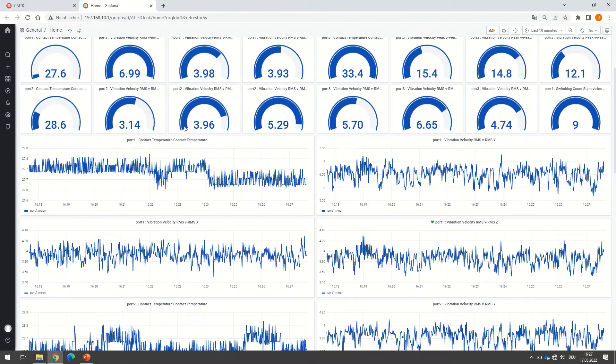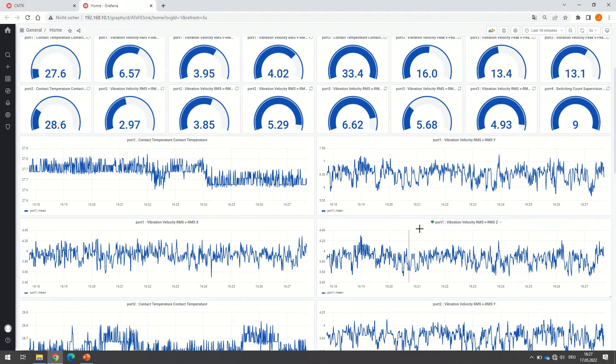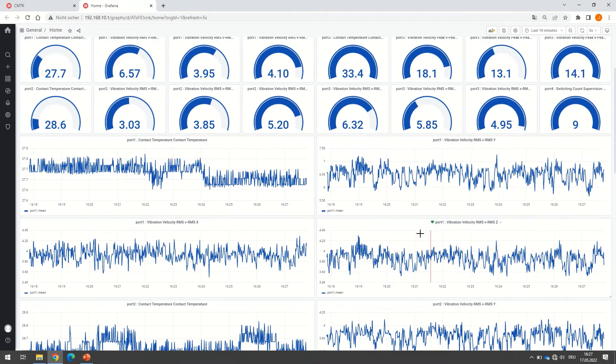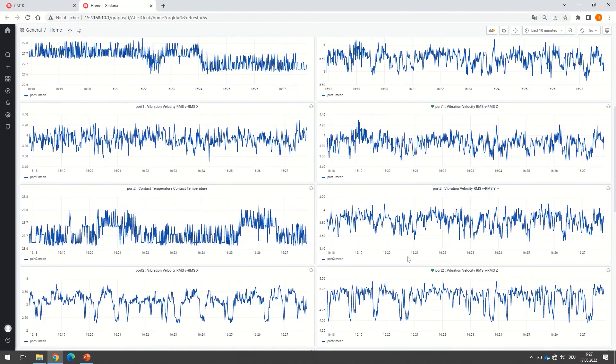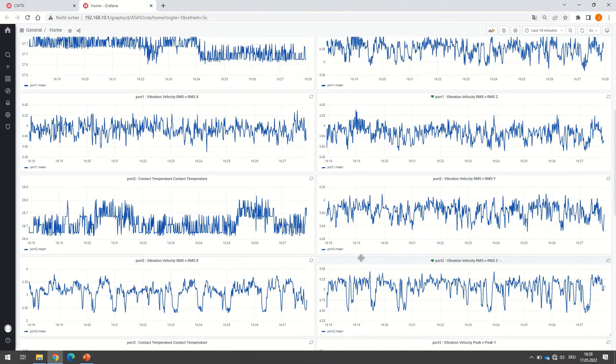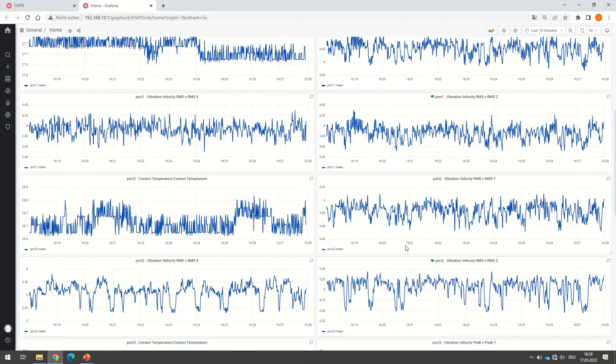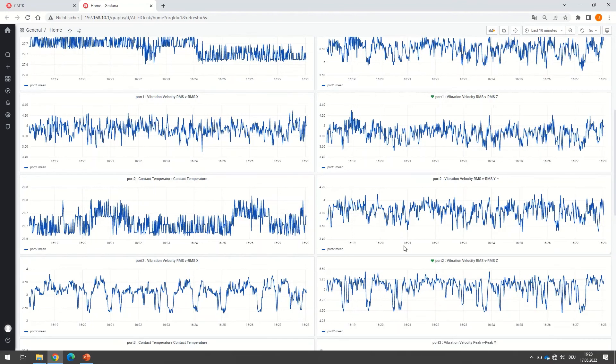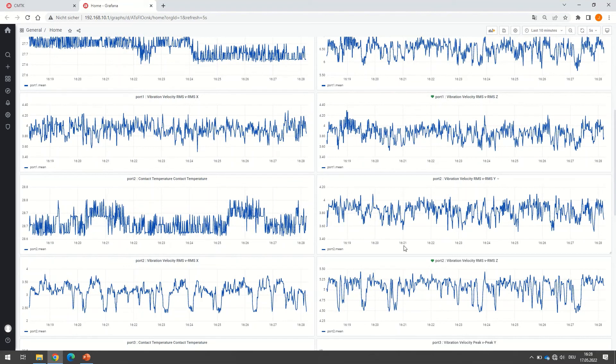For example, here we can see the four charts for the first BCM and here we see the vibration velocity in the Z direction. In the next four charts we see the process data of the second BCM and on the bottom right corner we see the vibration velocity of the Z direction of the BCM that is mounted on the fan. Both levels are below ISO standard pre-alarm level.